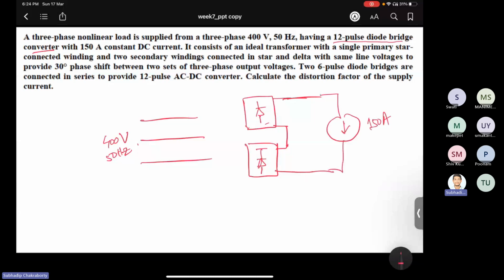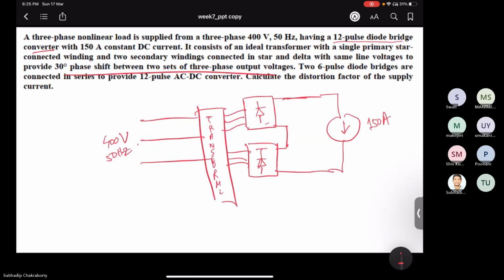You have some isolation arrangements with some transformers to get the phase shift, 30-degree phase shift you want, right? So you have one going here and another going here. So this is the transformer arrangement. So this is how the supply looks like. You have the isolation here, right? And the phase shift. Two sets of star and delta, that phase shift 30 degrees attained, and you feed the DBR based loads. So here is one DBR based load and here is another DBR based load, right?